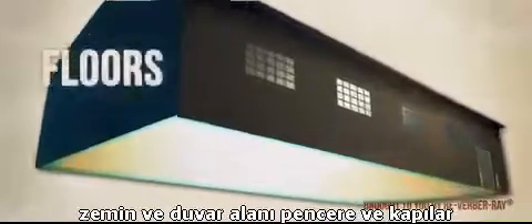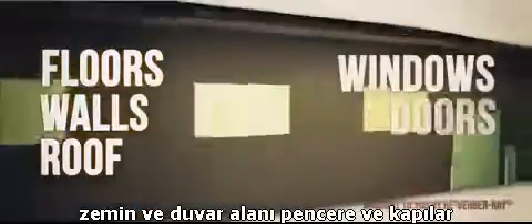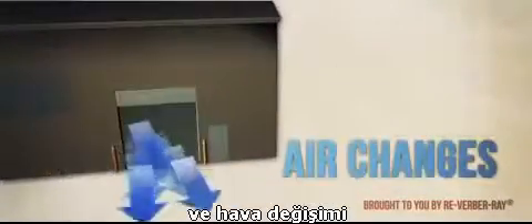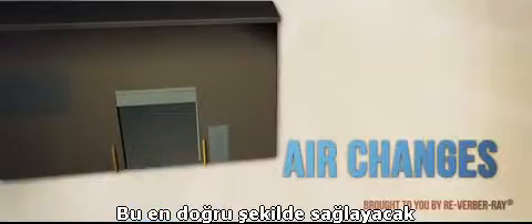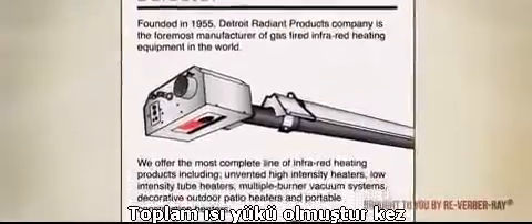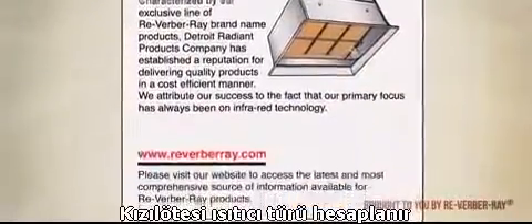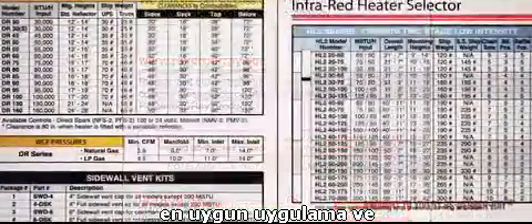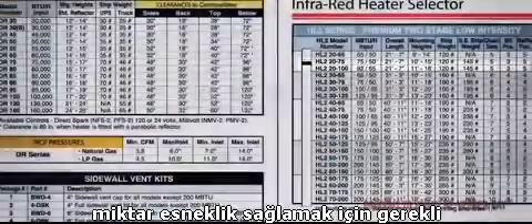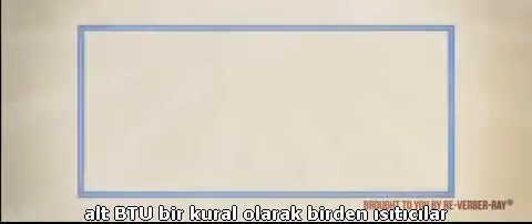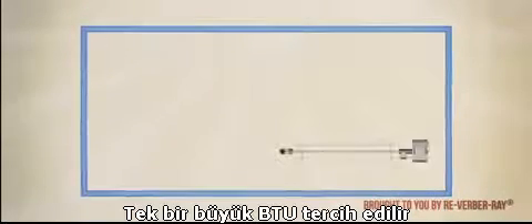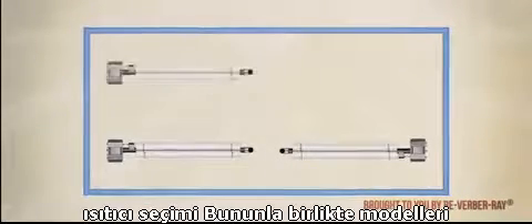Factors to include are floor and wall area, windows and doors, and air changes. This will most accurately provide the necessary BTU heat load requirements. Once the total heat load has been calculated, the type of infrared heater that best suits the application and the quantity required to offset the calculated heat load can be determined. As a rule, multiple heaters of lower BTUs are preferred over single large BTU models.